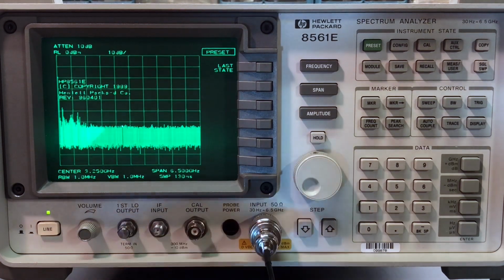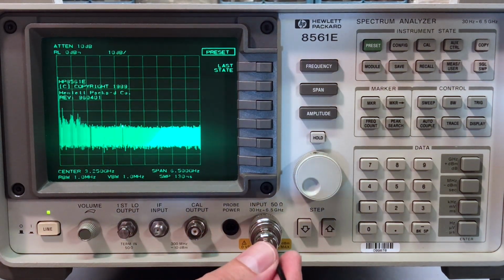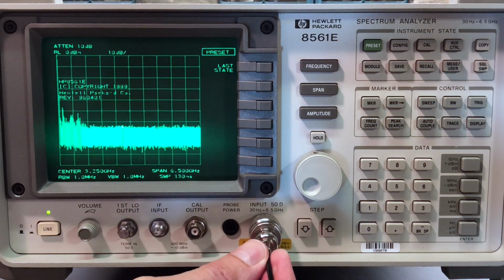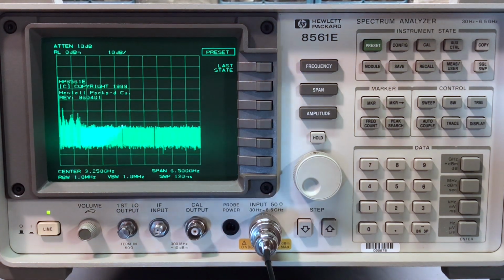So this coax cable is coming from my 10 megahertz frequency oscillator. It's a GPS disciplined oscillator, so it's synchronized to the GPS time signal or time standard. So very, very accurate 10 megahertz reference, and it's basically accurate down to 100 microhertz. I'm looking at its display right now, and it's 10 followed by all zeros down to 100 microhertz. So very, very accurate signal. So we can check the accuracy of the spectrum analyzer with this.